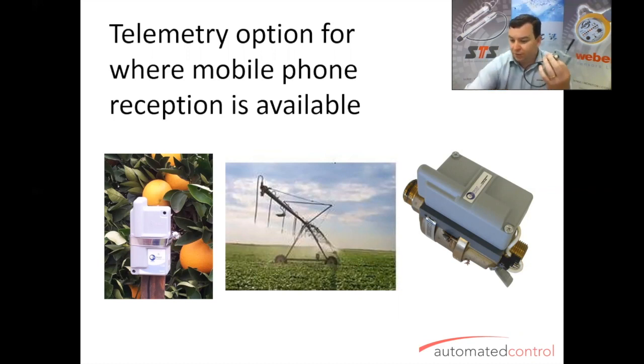You can plug a 4 to 20 milliamp sensor — for example, if you've got a tank and you want to plug a pressure transmitter on the bottom of it, plug that straight on there. Suddenly, you'll have remote monitoring of a tank pressure, which will give you a tank level straight out of the box. These are all the components you need. The setup isn't that complicated — once you get to the software side, it's really user-friendly.